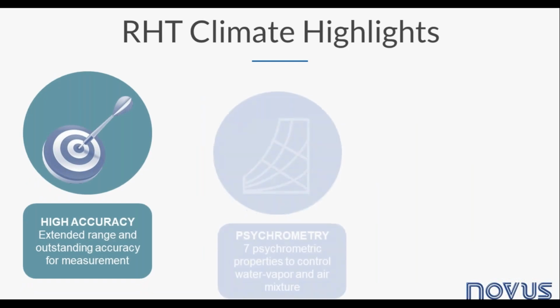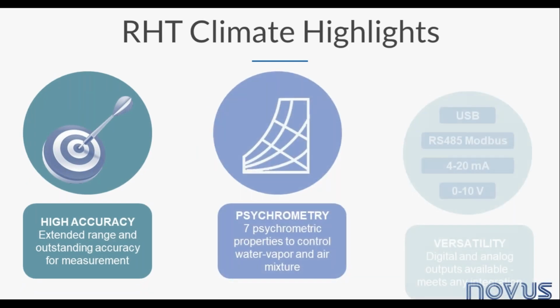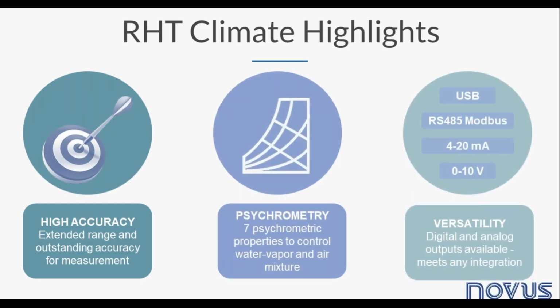With two analog outputs, one typically for temperature and the other for humidity or any psychrometric property, configurable by software, the output signal can be 4 to 20 mA or 0 to 10 volts, with the possibility to force the output signal for commissioning tasks. All settings...